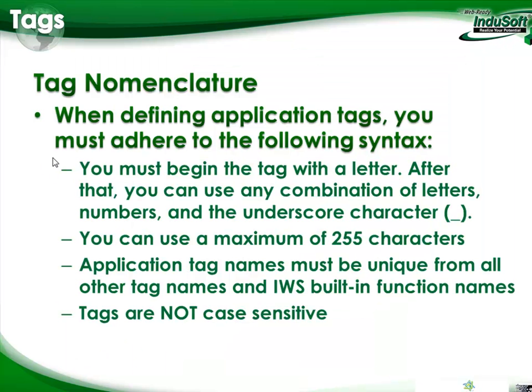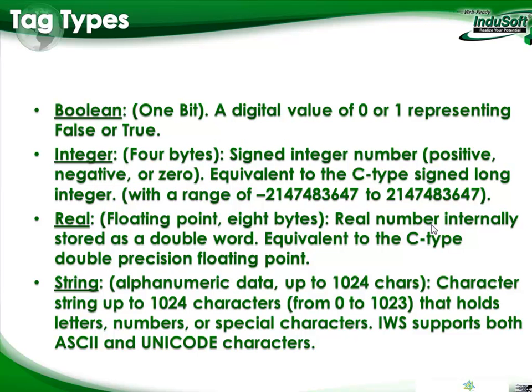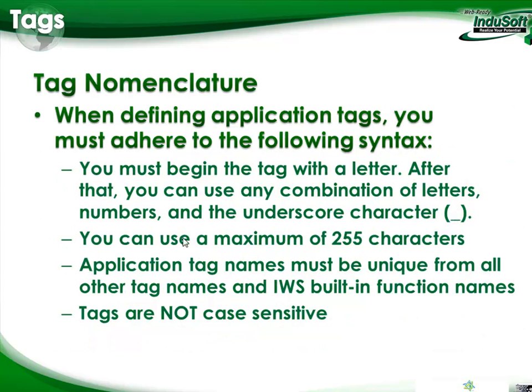Now, tag naming and conventions. When defining application tags or project tags, you must adhere to the following syntax: they must begin with a letter. After that, you can use any combination of letters, numbers, and the underscore character. You can use a maximum of 255 characters for the tag name. That seems like a lot, but when you start getting up to 10 million tag names in a project, it becomes vital to have plenty of character space so your tag names can be unique.